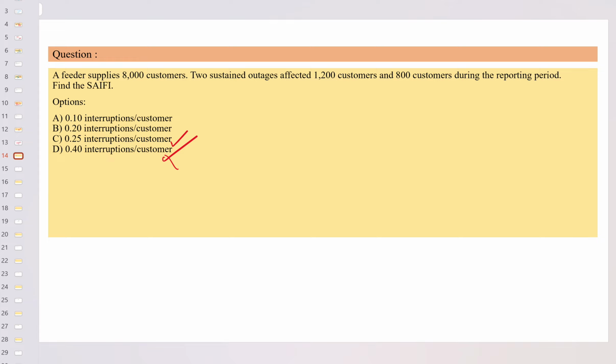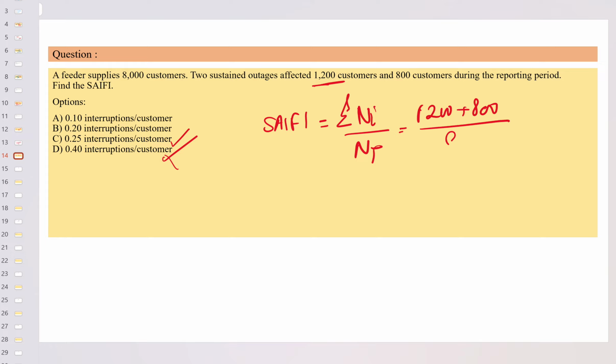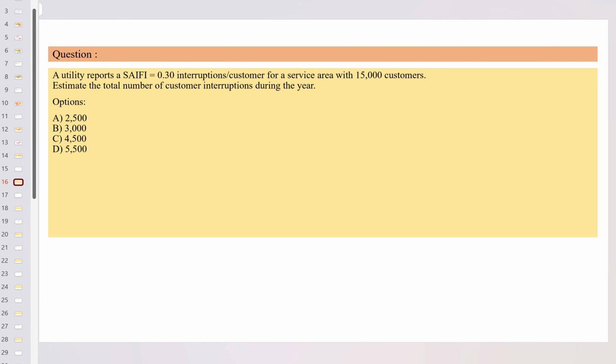That is true. We already know what SAIFI is: summation of Ni, total number of interruptions, divided by total number of customers. Sum of interruptions is 1200 plus 800, divided by 8000, which gives 0.25 interruptions per customer. But when you see the sustained interruptions affecting 1200 customers and 800 customers, that is fine. So by definition, SAIFI is this. Let's see some reverse way to look at it.